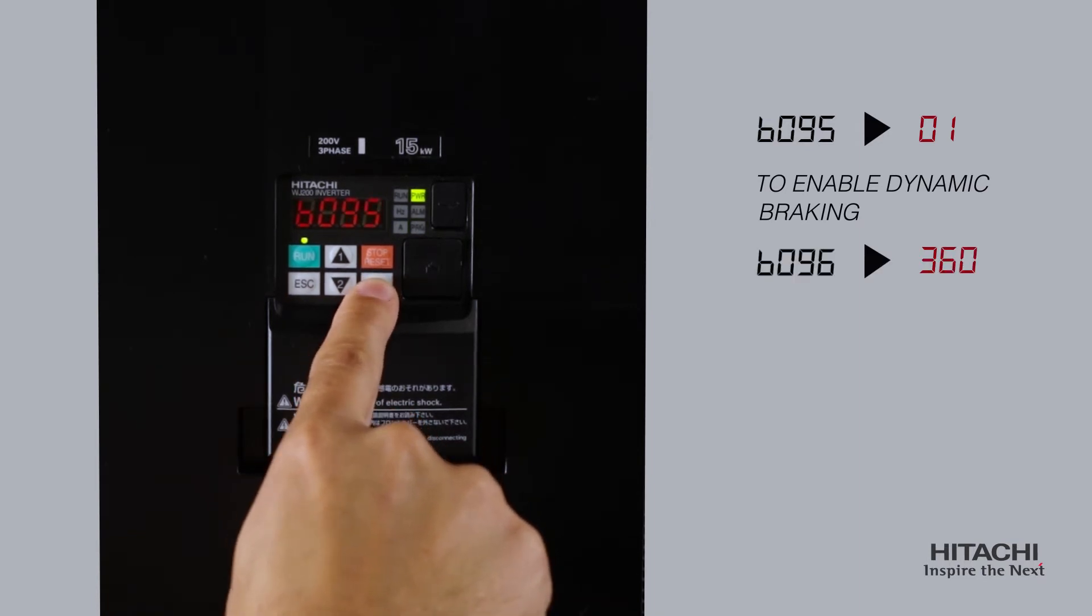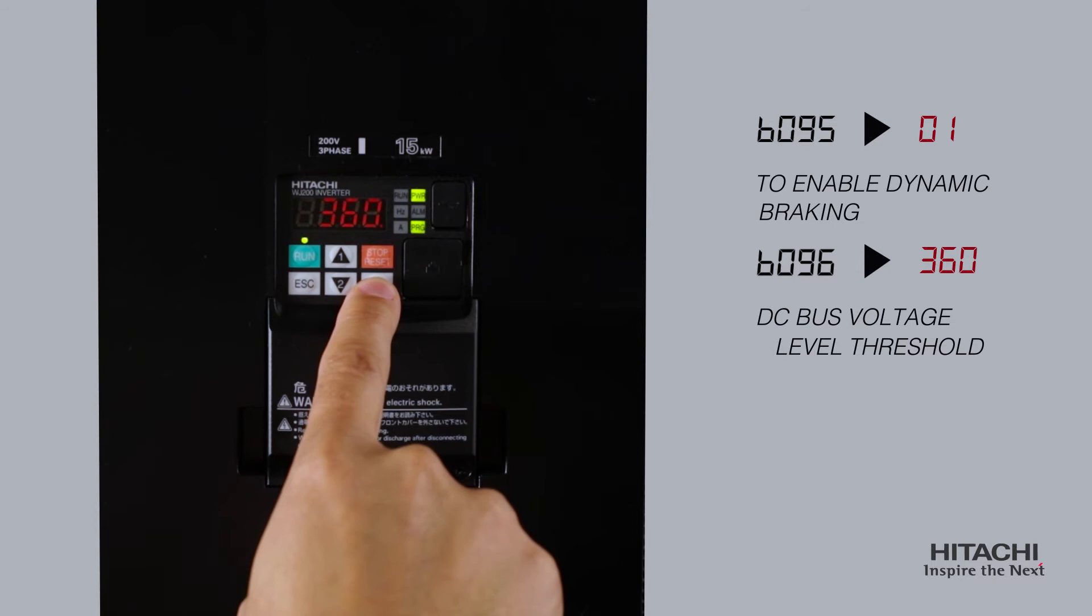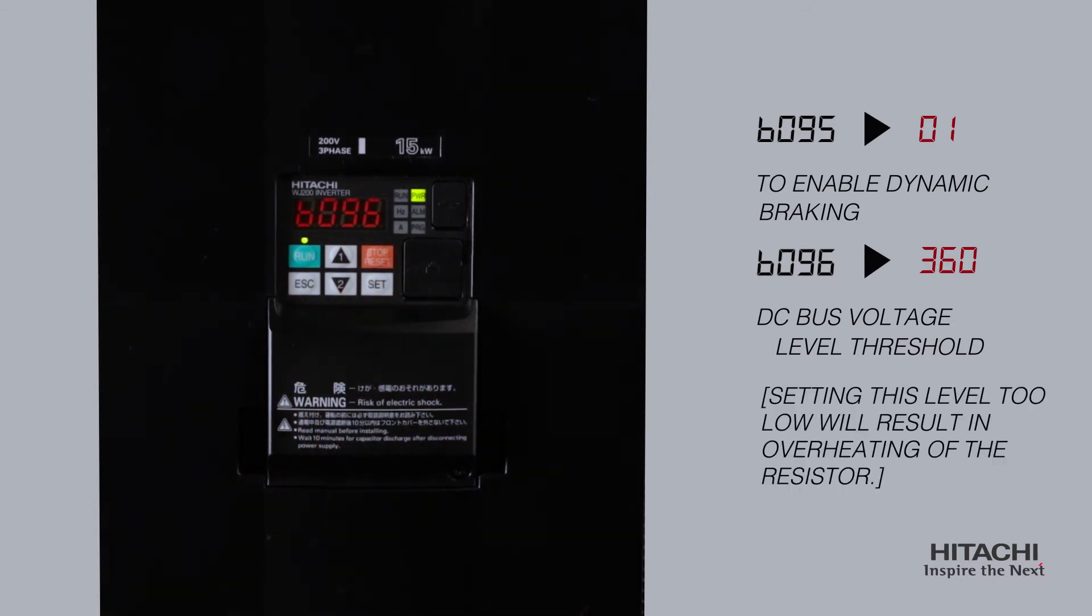Set B96 to the desired DC bus voltage level threshold. Default is 360 or 720 volts. Please note, setting this level too low will result in overheating of the resistor by activating the braking circuit prematurely.